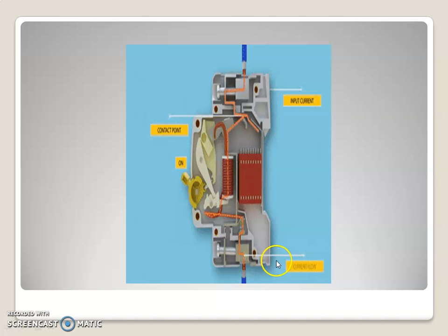Now, the operation of the MCB includes two stages, that is the thermal operation and the short circuit operation, that is the overload and the short circuit, because MCB will operate in two ways. During the overload condition, that operation is called the thermal operation, and during the short circuit condition, that operation is called the short circuit operation. With the use of the bimetallic strip, the thermal operation is achieved in case of the overload condition. When the overload current flows through the MCB, the bimetallic strip gets heated and causes it to deflect.